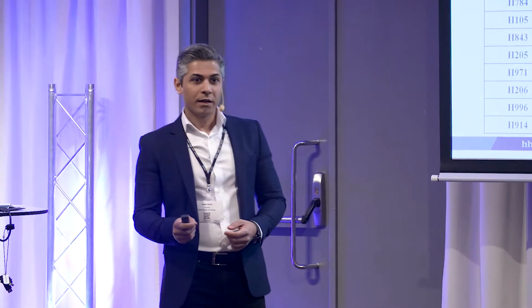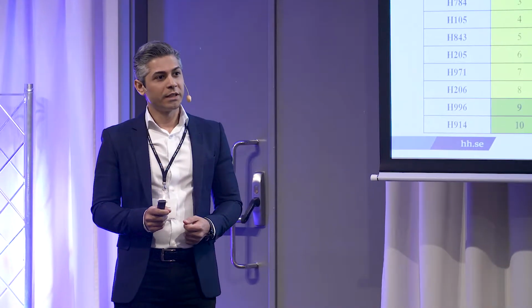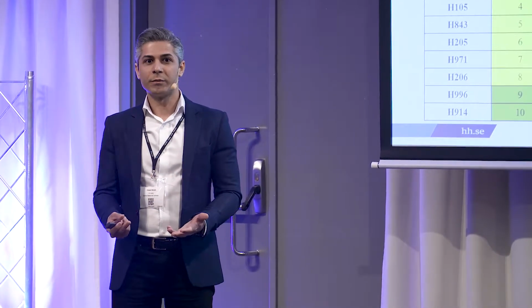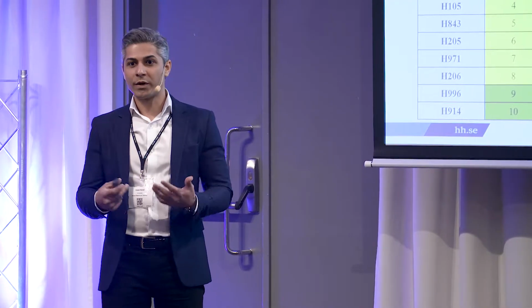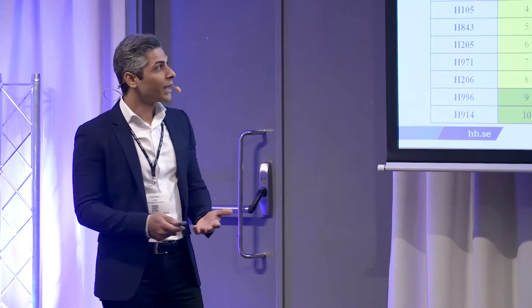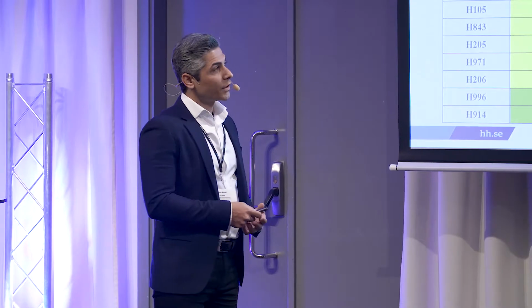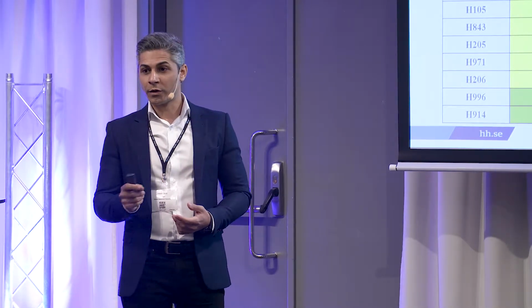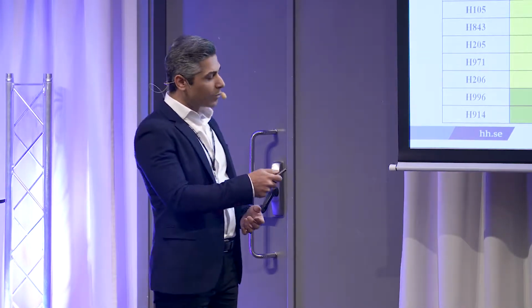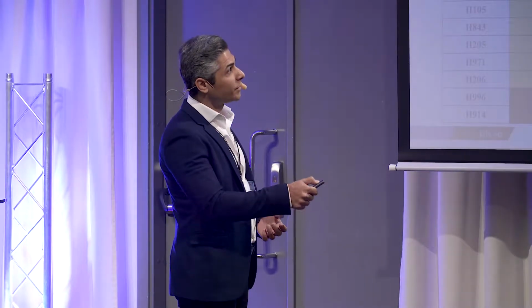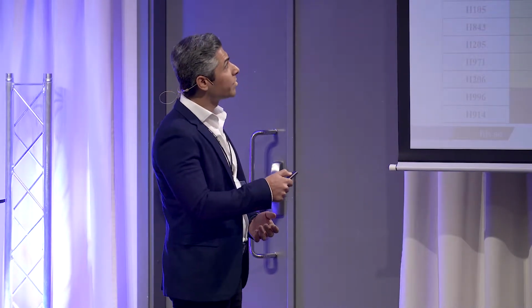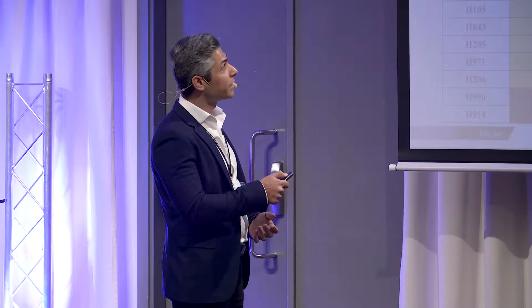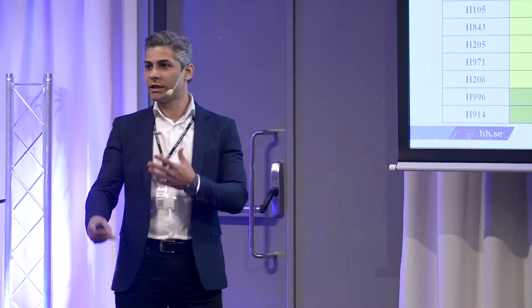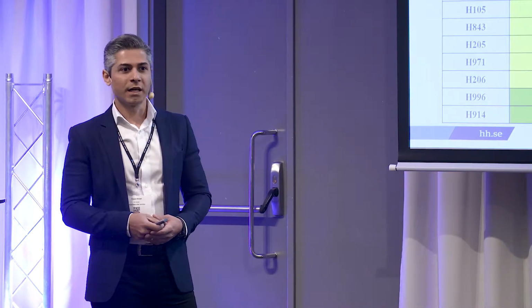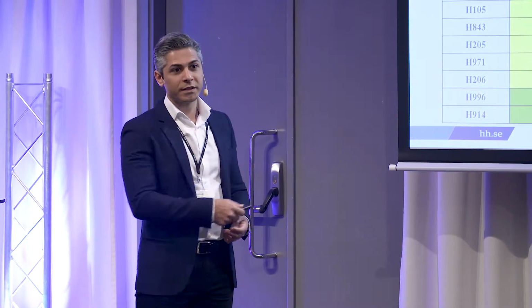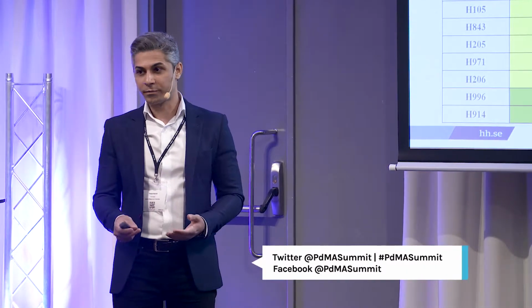As I mentioned, it's important to consider the reality of the power cable as a repairable component. We show that if the cables are considered as repairable or non-repairable, not only would the baseline failure rates be different, but also the impact of different factors and the significance level would be different. Consequently, they produce different ranking lists, and the differences in some cases are not negligible.